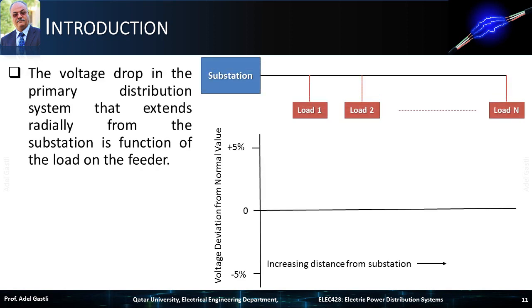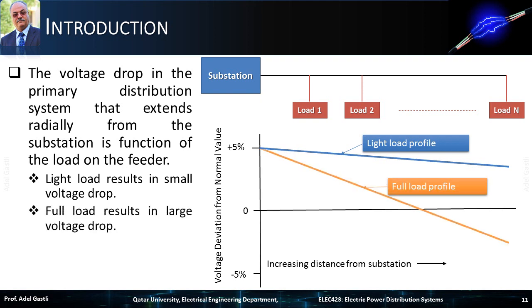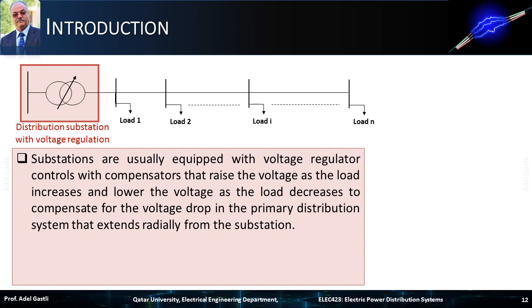It is worth mentioning that the voltage drop in the primary distribution system that extends radially from the substation is a function of the load on the feeder. Consequently, light load results in small voltage drop, while full load results in large voltage drop. Substations are usually equipped with voltage regulator controls with compensators that raise the voltage as the load increases and lower the voltage as the load decreases, to compensate for the voltage drop in the primary distribution system that extends radially from the substation.